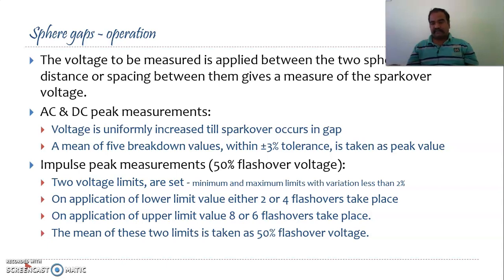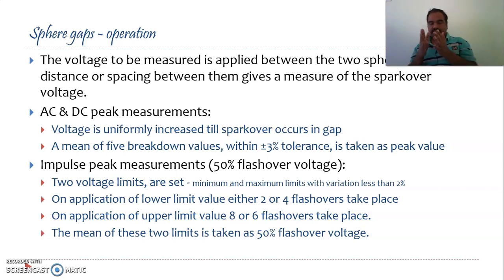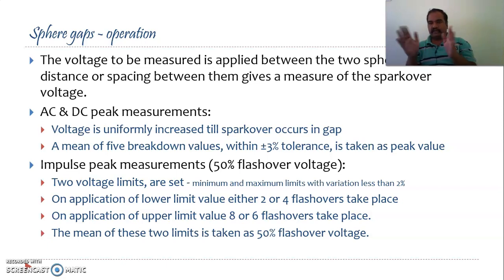In the case of impulse voltages, the impulse voltage will have a 50 percent or 100 percent flash-over voltage. To measure 50 percent impulse flash-over voltage, two voltage limits are set within a range of 2 percent — one maximum and one minimum. At application of the lower limit, 2 or 4 flash-overs must take place; at the higher limit, 8 or 6 flash-overs. In total, 10 flash-overs must happen. The mean of these two limits is taken as the 50 percent flash-over voltage.